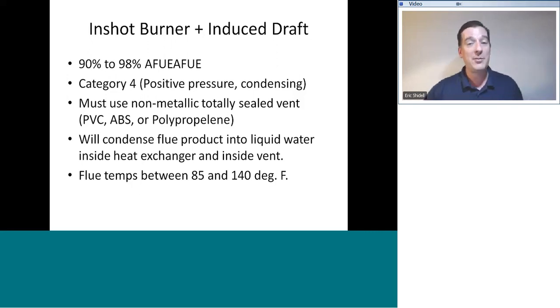Apparently, the furnace manufacturer thought there was one. That's why they put it that way in writing. And if you take it upon yourself to do something else and there's ever a problem, now the furnace manufacturer has no liability, but you certainly do. So follow those instructions to the letter. If it says you use brand ABC, use brand ABC. Don't use brand XYZ unless it says you can. And if it doesn't say anything about polypropylene vent at all, guess what? You can't use it. So be aware of that.